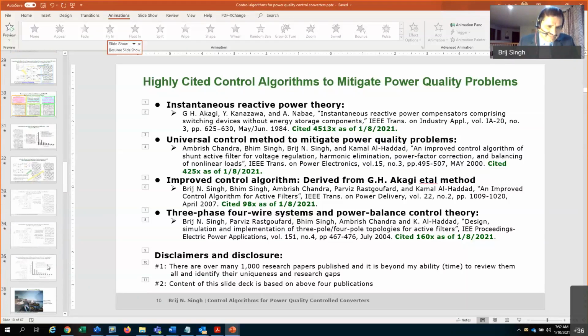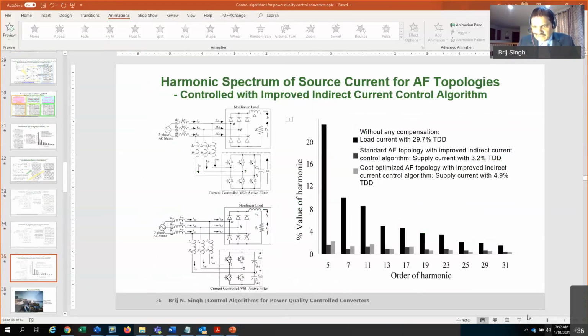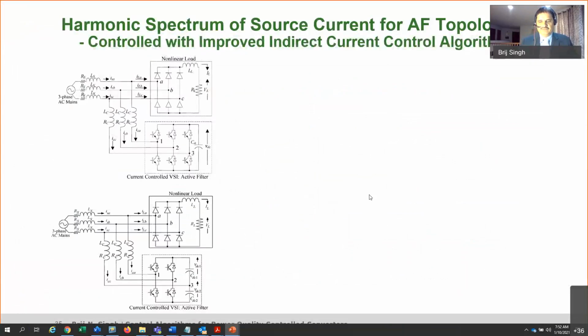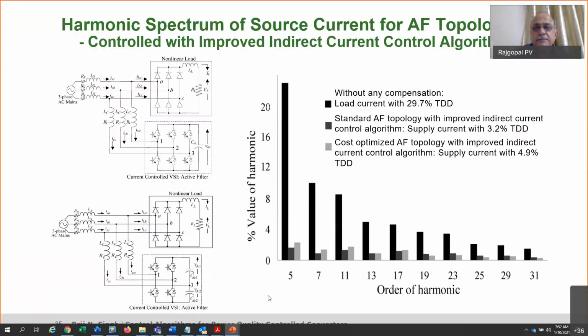For an RL load, THD is 30%, while IEEE 519 or other standards like IEC and UL require you to go below 5%. Looking at the dominant harmonics, the 5th and 7th, these are odd harmonics, and with a balanced load you usually don't get even harmonics. The 5th is touching roughly 25% or so, and the 7th is above 10%.